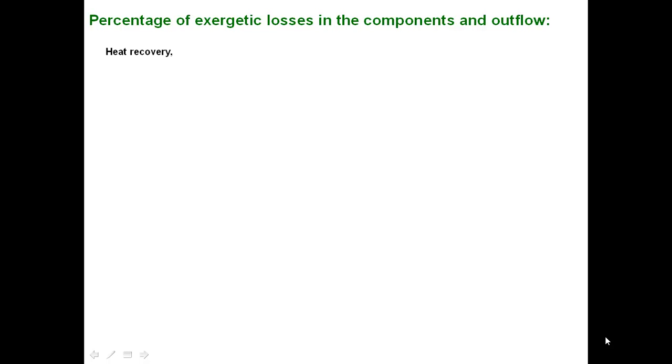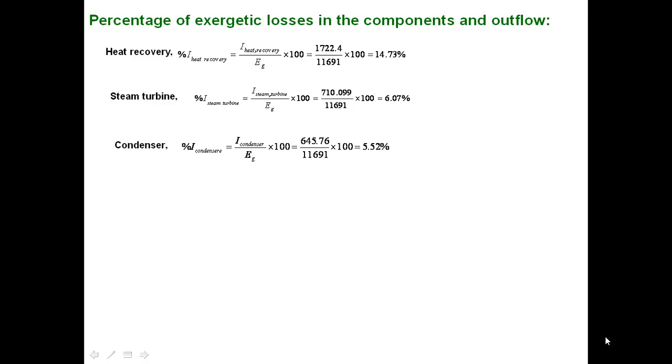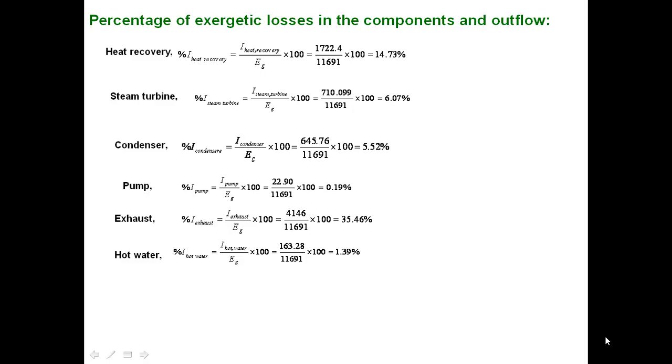Therefore, the percentage of irreversibility in the heat recovery is identified as 14.73%. It is the ratio of irreversibility in the heat recovery and exergy value of hot gas. Similarly, for the steam turbine, it is 6.07%. For condenser, it is 5.52%. For pump, 0.19%. It is very low, it is minimum value. Exhaust is very high, it is 35.46% because the hot gas exit temperature from heat recovery is considered as 200 degree centigrade. Similarly, the hot water coming from the condenser, the associated percentage of irreversibility is 1.39%.